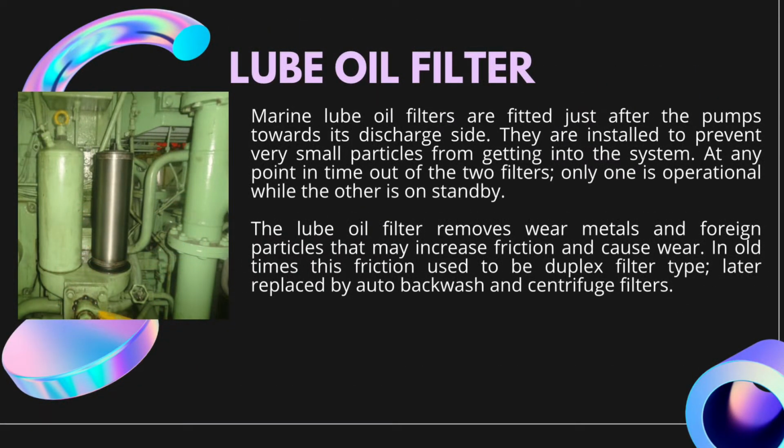Lube oil filter. Marine lube oil filters are fitted just after the pumps towards the discharge side. They are installed to prevent very small particles from getting into the system. This filter removes wear metals and foreign particles that may increase friction and cause wear. In old times, this filter used to be a duplex filter type, later replaced by auto backwash and centrifuge filters.